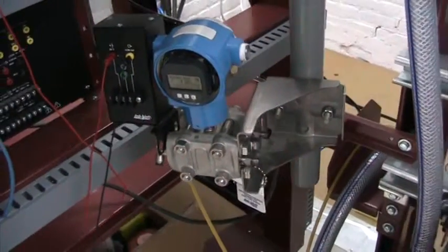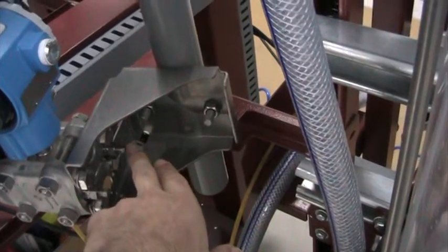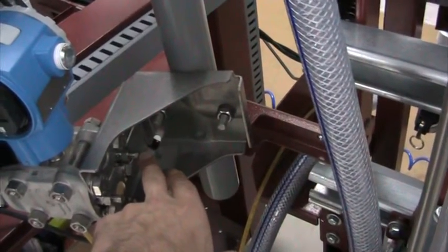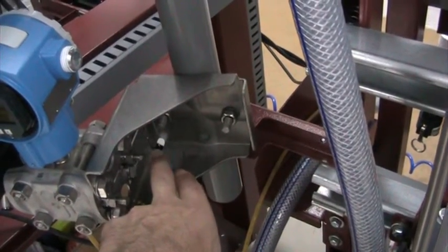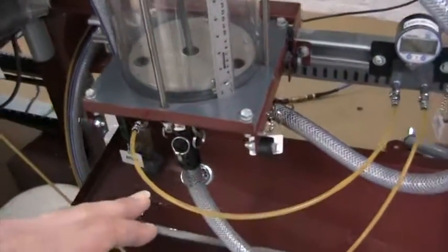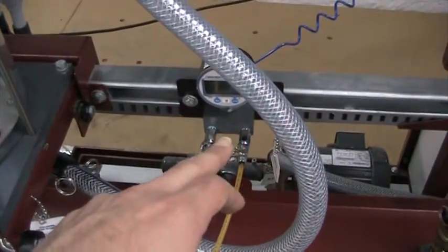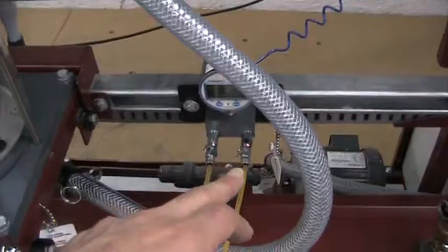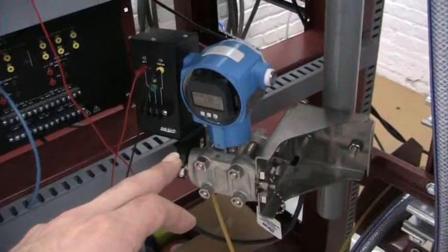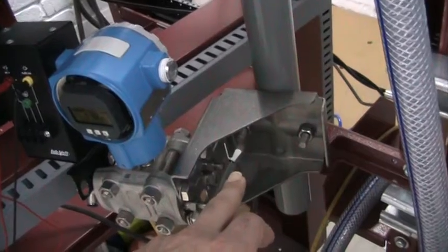And I have bled both instruments by purging any air in both instruments from this vent. So I have unscrewed this vent, and so water came through this tube, from this column through this tube into this instrument, the indicator, then out of this tube and into my differential pressure transmitter, and the air came out of this vent.